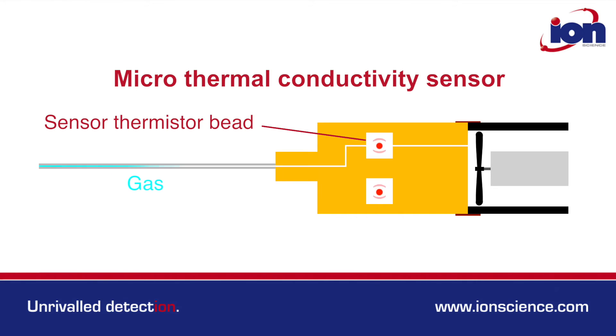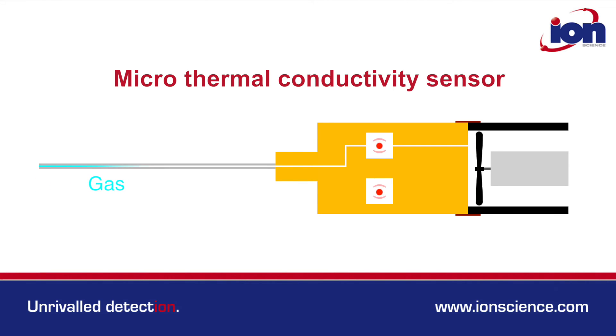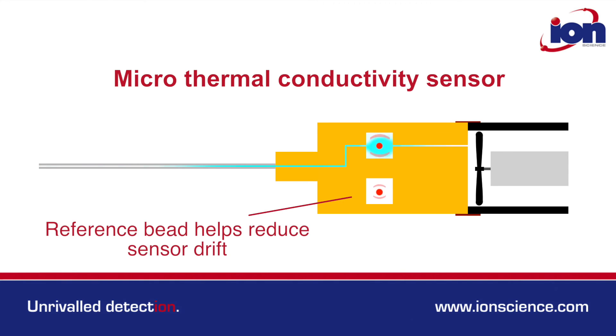When gases other than air pass between the microthermal bead and the thermal block, the rate of heat transfer changes, which in turn changes the resistance of the thermistor bead. It's this change in resistance that is measured and converted into a leak rate.